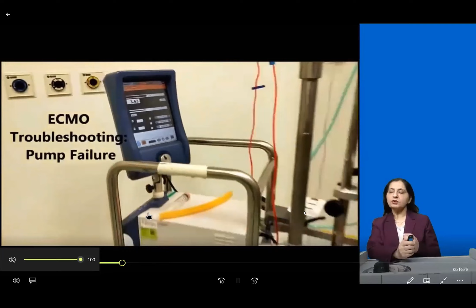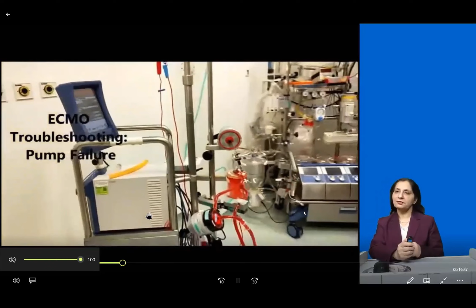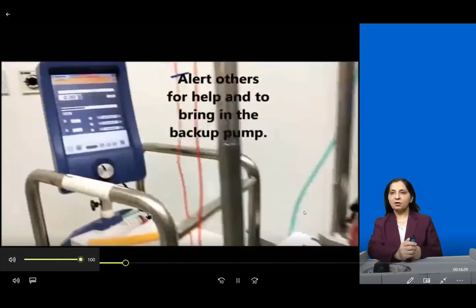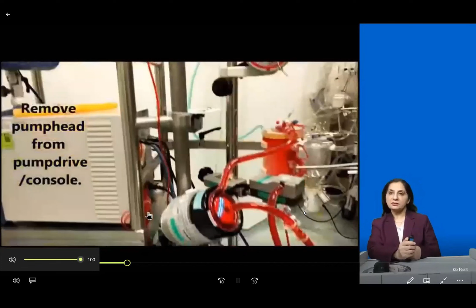So let's see what happens in a pump failure. If allowed to persist, there's a knocking of the pump head onto the console, which would always give rise to hemolysis. So clamp the post-oxygenator, alert, call for help, bring in the backup pump, switch off the AC power, and remove the pump head from the pump drive or the console.